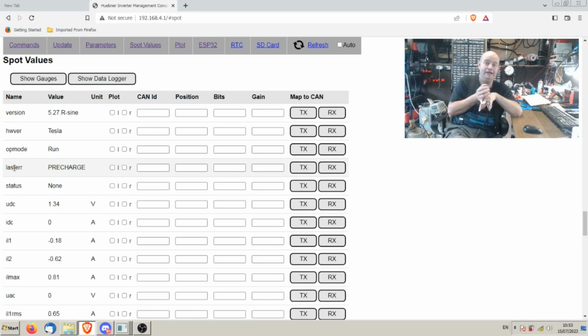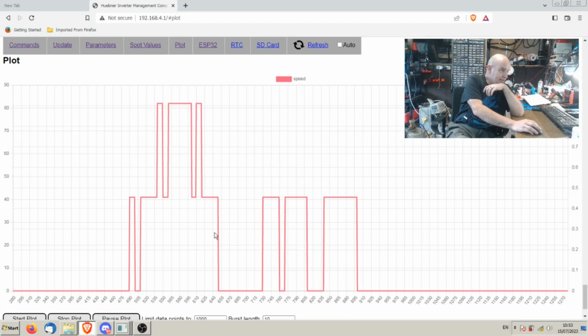If we had incorrect encoder values, incorrect encoder wiring, or a problem on our logic board with the encoder circuit, that's where it would show up. It'll either show up in the graph, where instead of this making sense, with a nice low 80, 40 RPM reading, the graph goes crazy and tells us we're at 16,635 RPM or something, or we just get a flat line. If you get a flat line or a crazy graph at this point, stop, take a breath, and trace down your encoder problems.